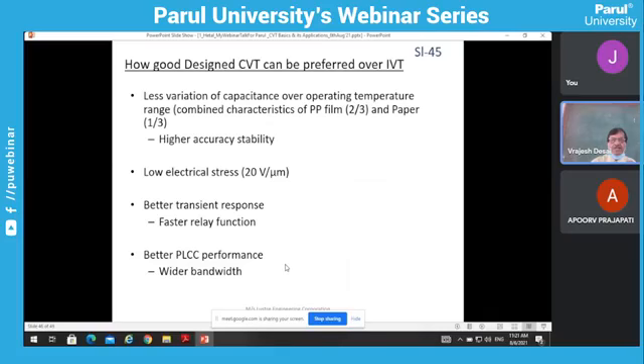Now, coming to the last few slides, how the CVT is preferred over IVT. As I already told you, the CVT gives very good accuracy, because the PP film and paper hardly get any temperature rise. So there is no variation in the capacitance, which means the output voltage on the secondary side also remains constant. That is one benefit. Second, it is designed with a very low electrical stress, that is 20 volt per micrometer, which is nothing but 20 kV per mm.